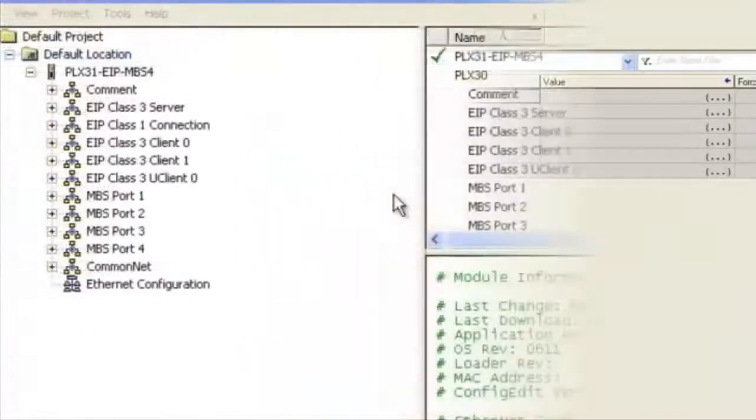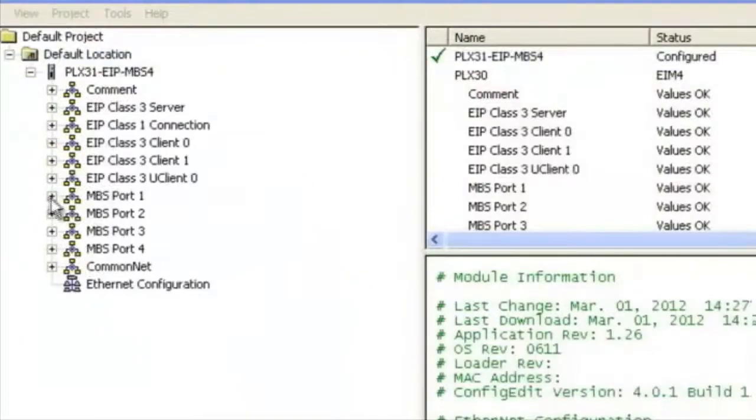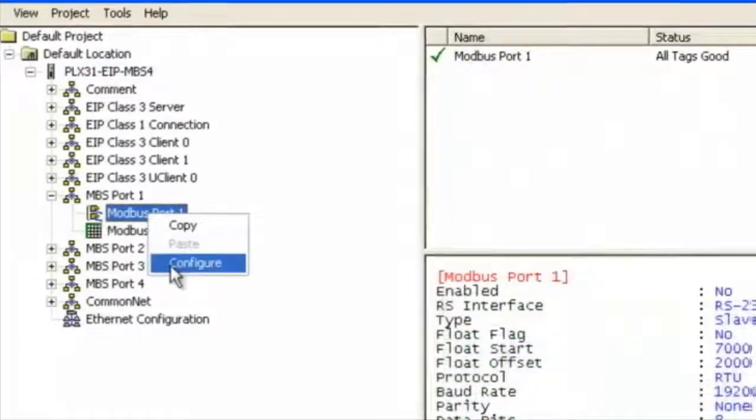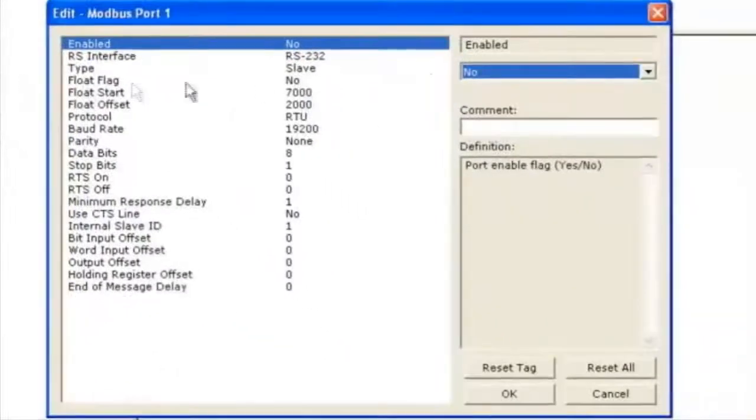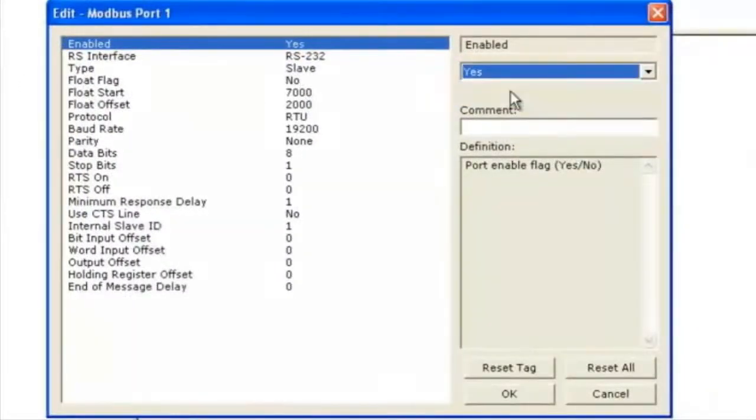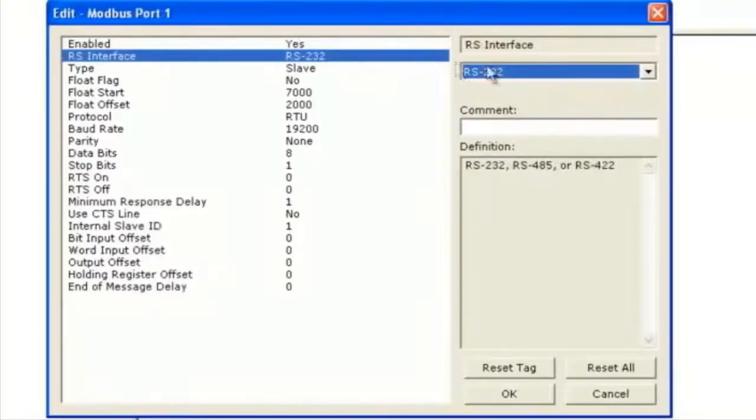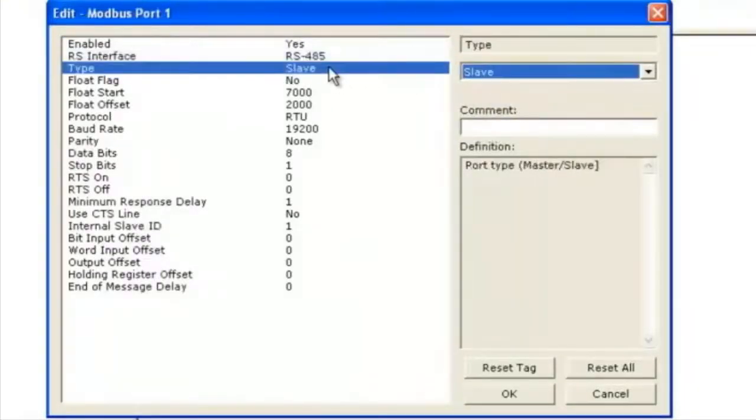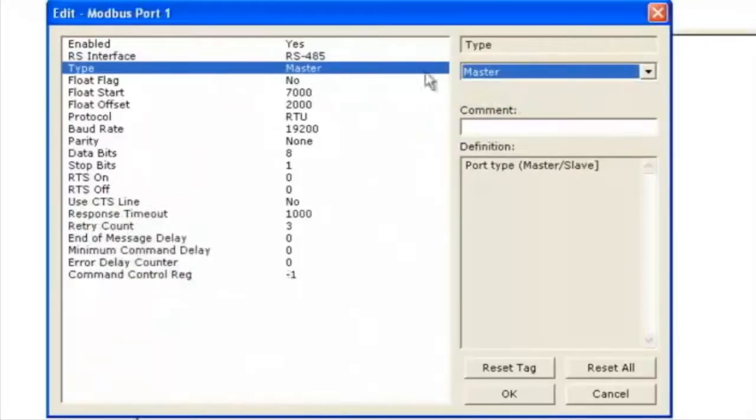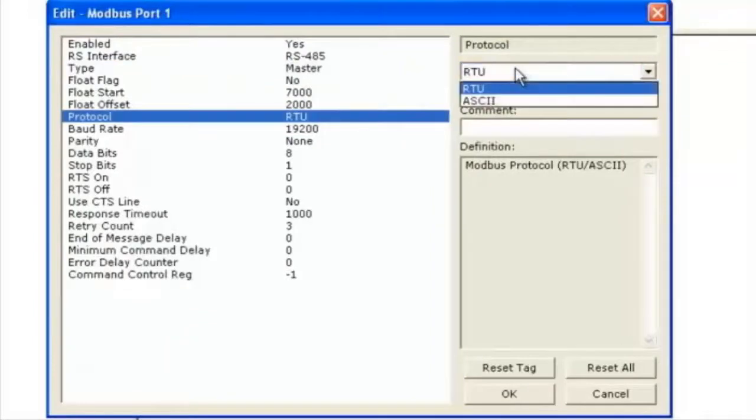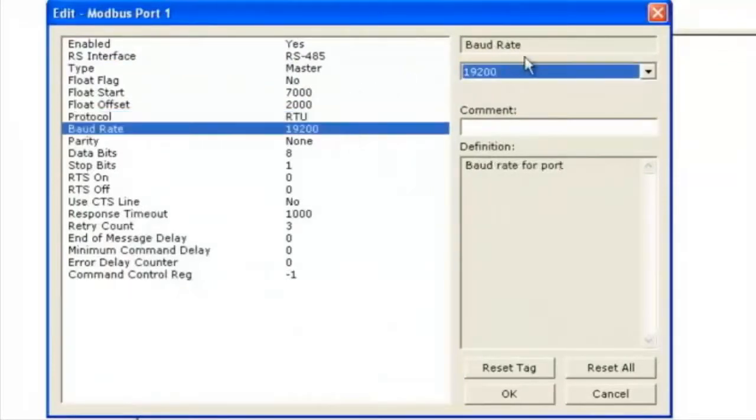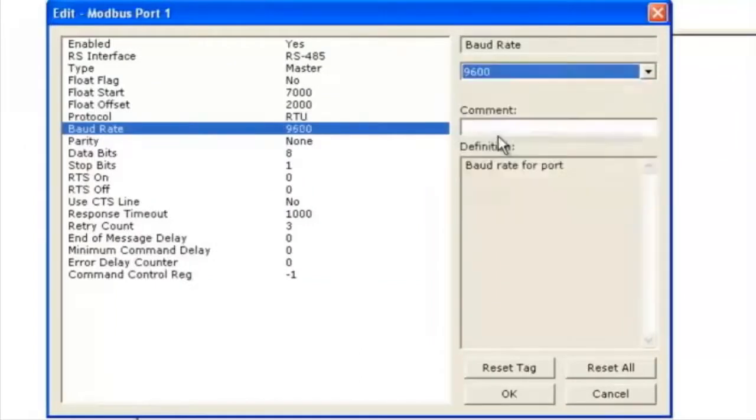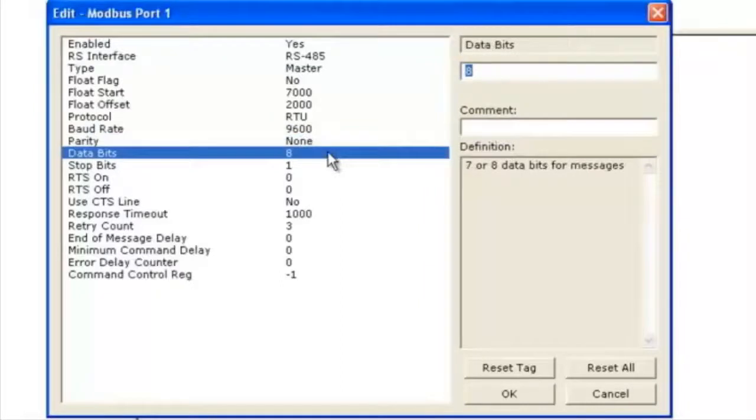We'll right click on Modbus port 1 and click configure. First option is enabled. We're going to choose yes. Here's the RS interface. We're going to choose RS 485 for this application. The type is master and protocol is RTU. Baud rate is 9600. Parity none. Data bits 8. Stop bits is 1.